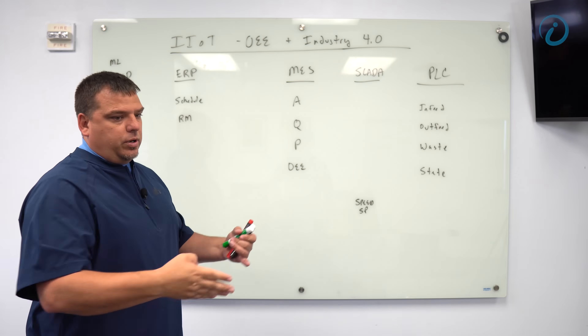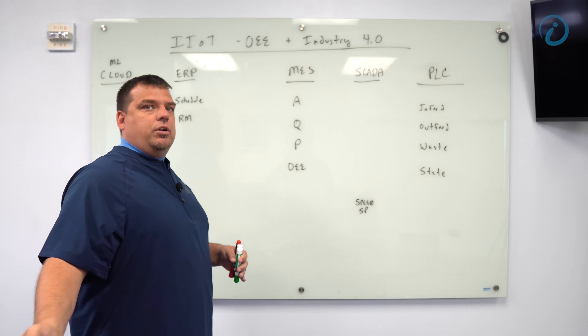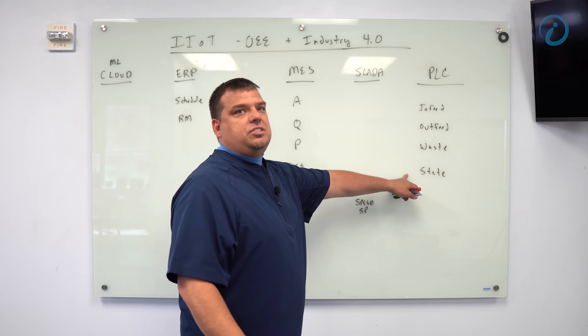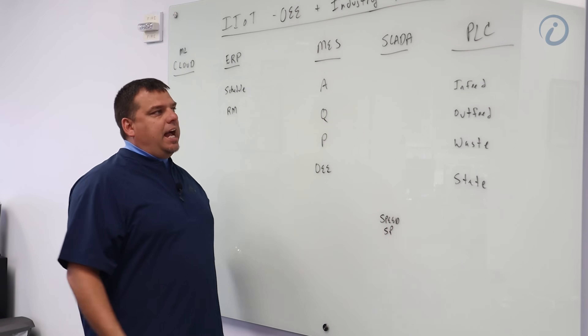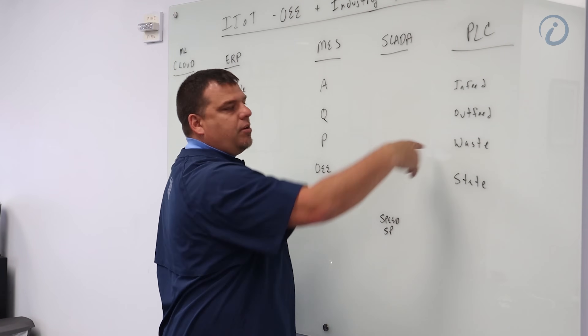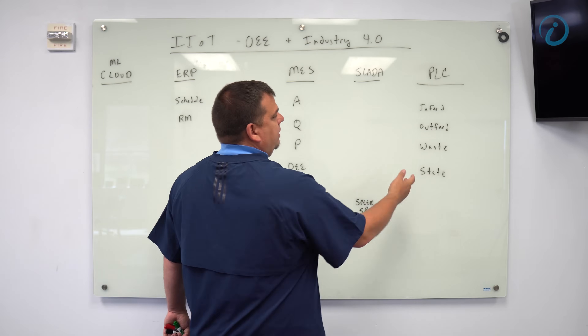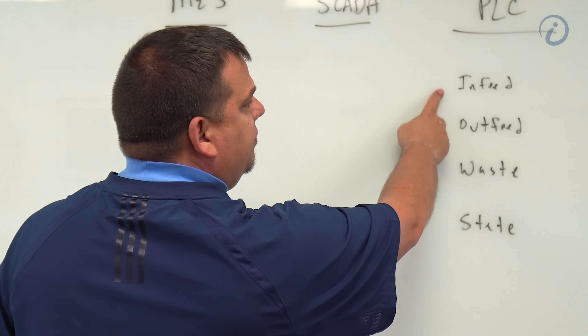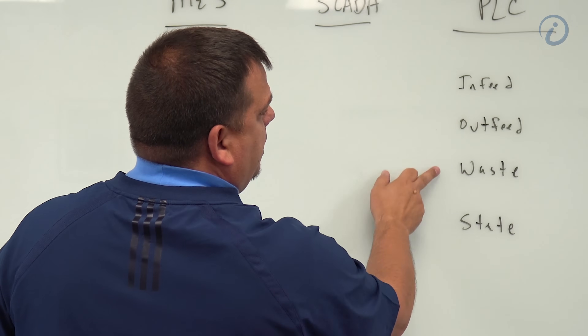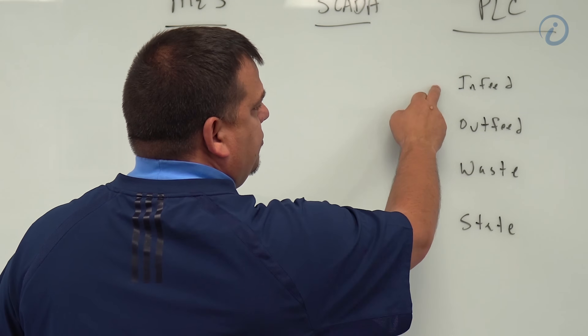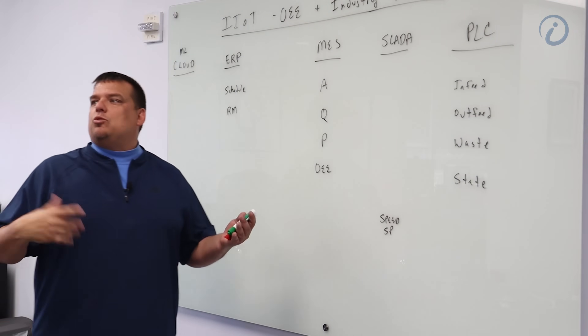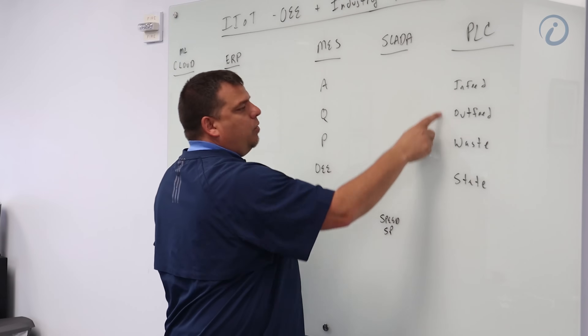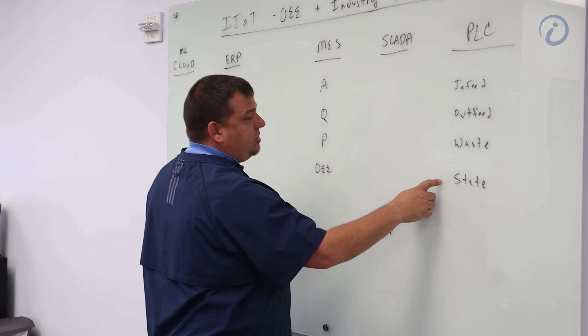That is: what's the total number of widgets fed into the machine, what's the total number produced going out, what was the total number of waste, and what's the state of the machine at any given time. If I have two of these counts, I can derive any third one. I can add outfeed and waste to get infeed, or subtract waste from infeed to get outfeed. Not every machine will have all of these, but they will have state.